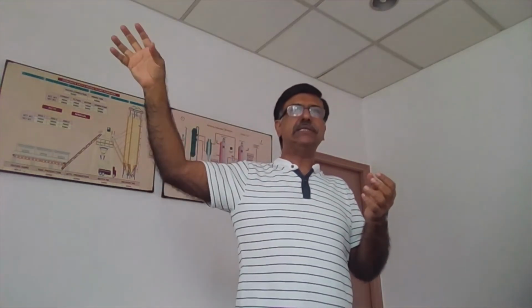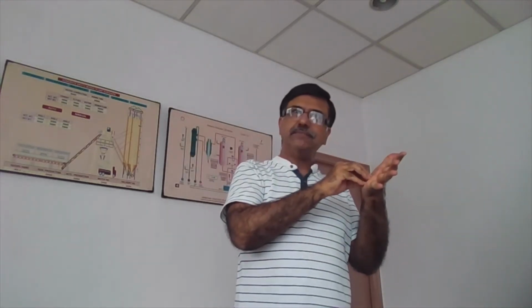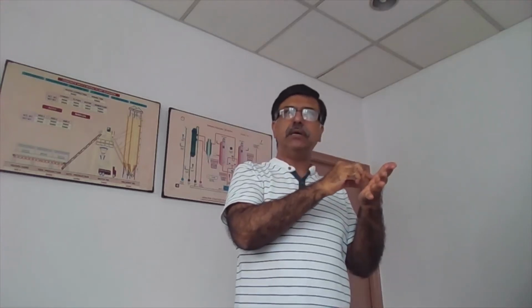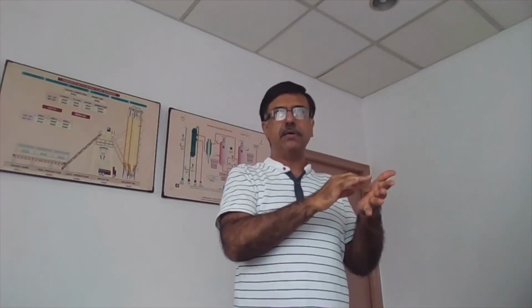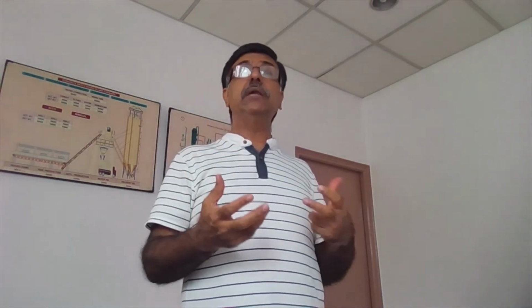So you have an object in the SCADA, you will attach it to a device, and that device will be attached to a memory once you know the memory map, right? So similarly for voltage, current, kVA, and so on, in the memory map there will be two types of memories. One read only, one read write.